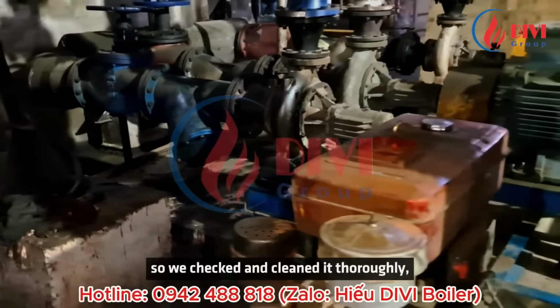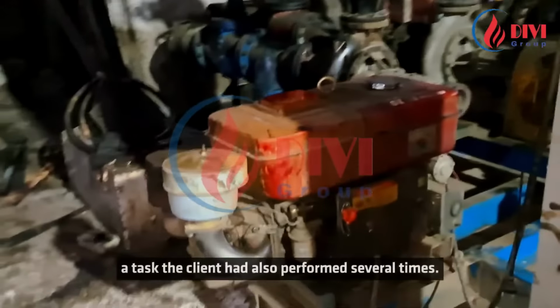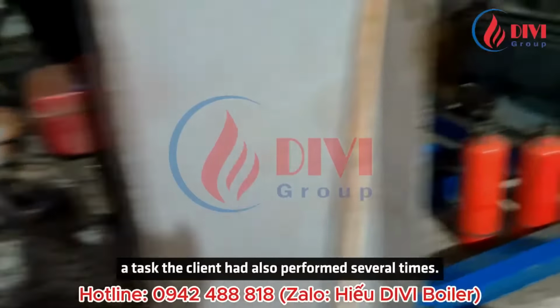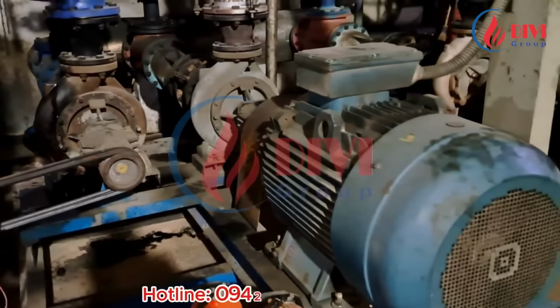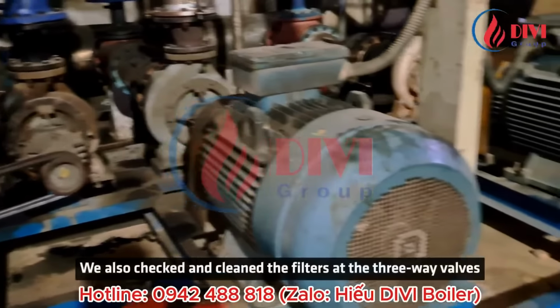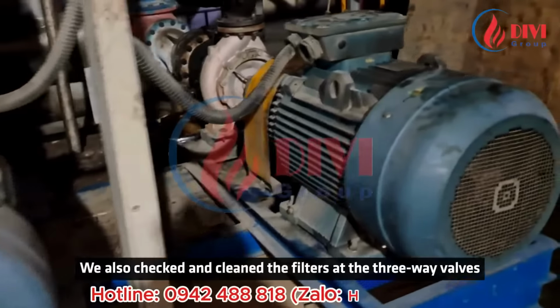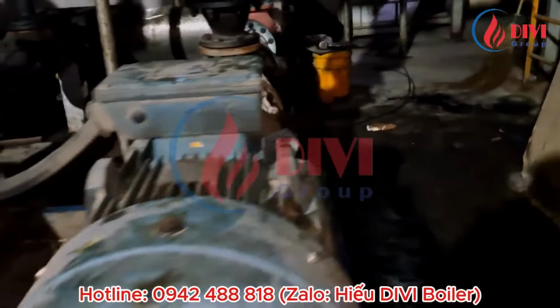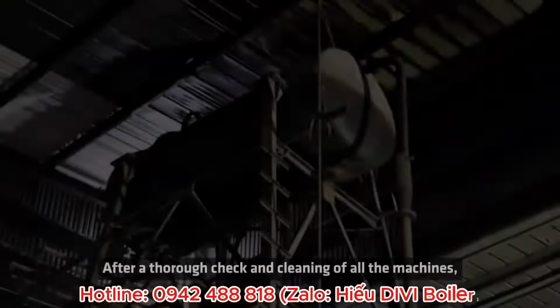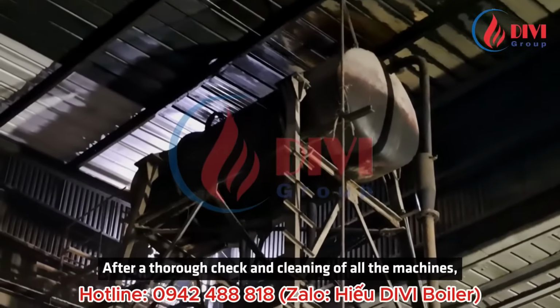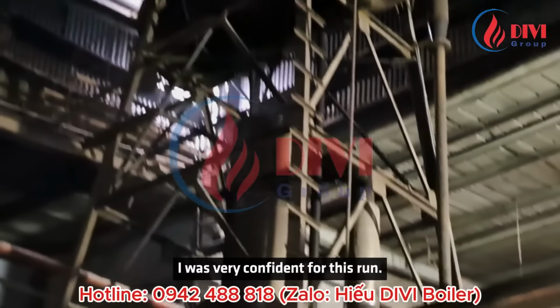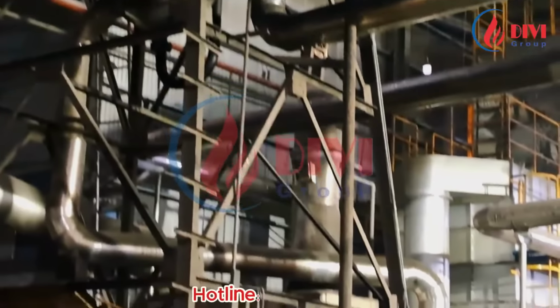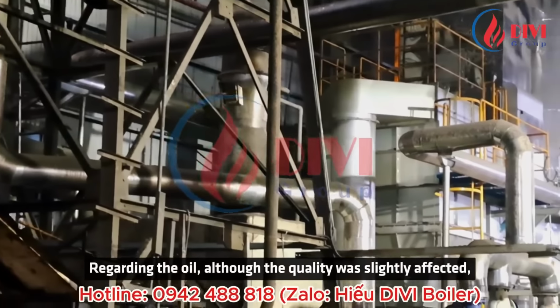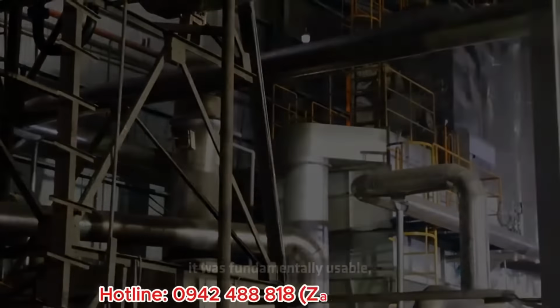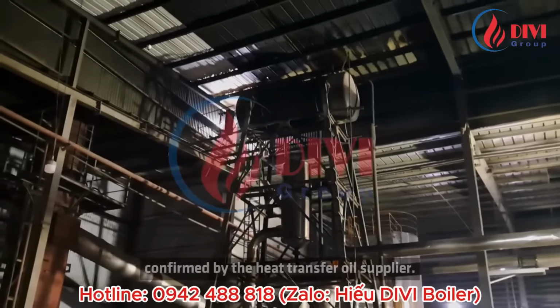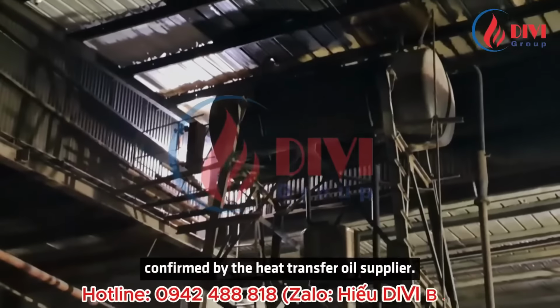So we checked and cleaned it thoroughly, a task the client had also performed several times. We also checked and cleaned the filters at the 3-way valves and inside the expansion tank. After a thorough check and cleaning of all the machines, I was very confident for this run. Regarding the oil, although the quality was slightly affected, it was fundamentally usable, confirmed by the heat transfer oil supplier.